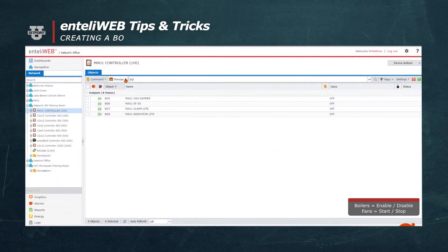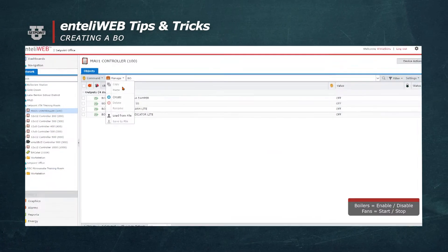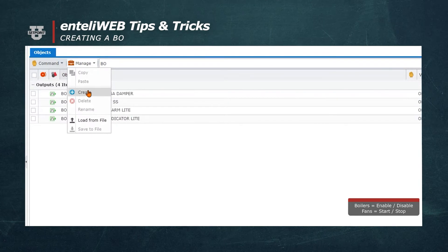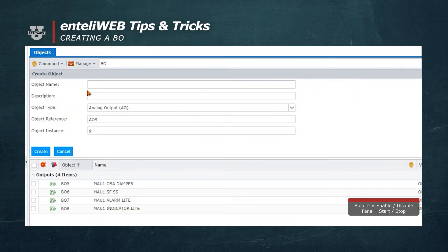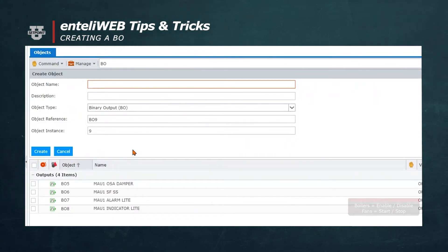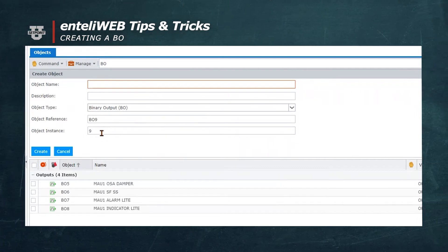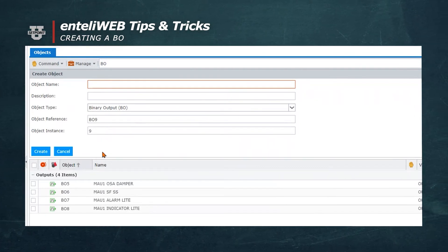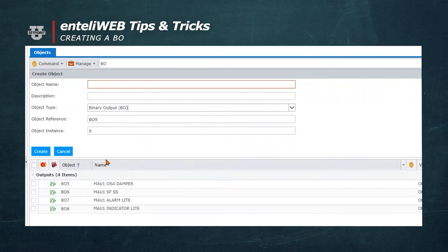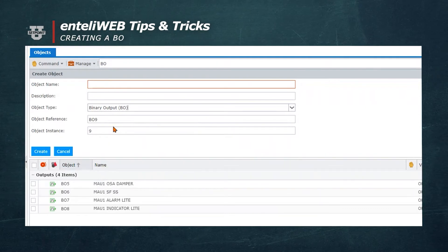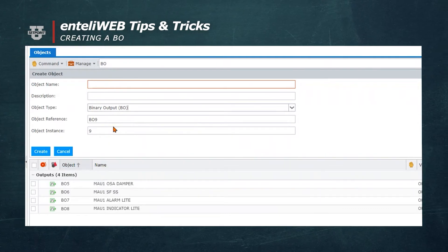Now let's create a binary output. We will go to Manage again, select Create, and select Binary Output as the object. You'll notice that it defaults to 9. Remember, it automatically selects the next number available, which may not be the next real number that's open, but it will be the next number in the sequence that's available.